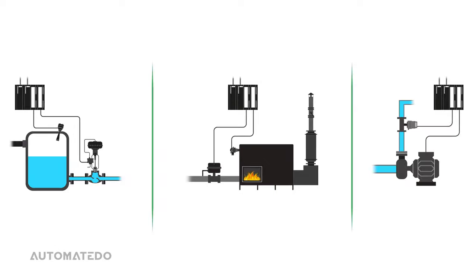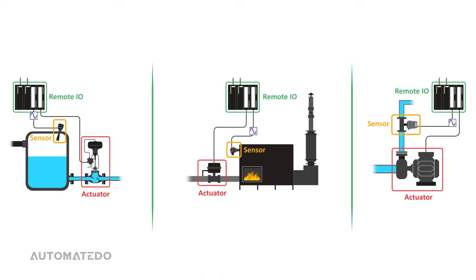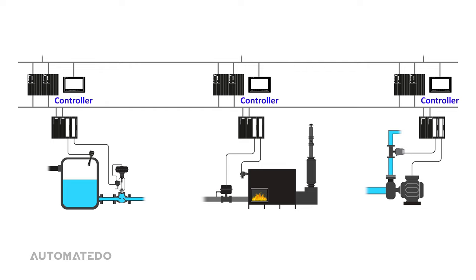To measure and control the different parameters in industrial processes, we need instrumentations like sensors and actuators located at the field device level. This level also includes distributed or remote IOs that can sense and control digital and analog signals by their I/O modules. The field devices and the controllers can communicate using almost any protocol compatible with the components, such as industrial Ethernet or PROFINET, PROFIBUS, etc.